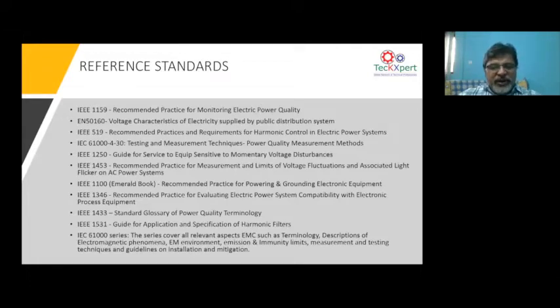So I would say the first three standards, the 1159, 50160 and 519, should be the three governing standards when you look into power quality. Because 1159 talks about voltage quality and current quality, IEEE 519 talks about harmonics, and 50160 talks about the voltage quality of the utility supplier. Now, for example, if you have BESCOM as a power supplier, 50160 governs the voltage quality of BESCOM supply. But you as a consumer, if you are running a power electronic device, then IEEE 519 governs the harmonic standards. 1159 governs all aspects of power quality.